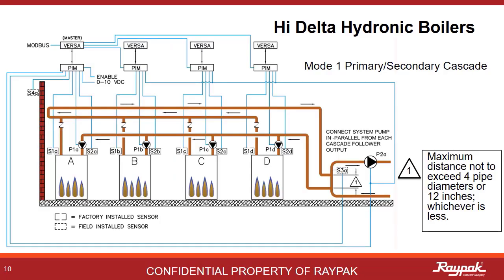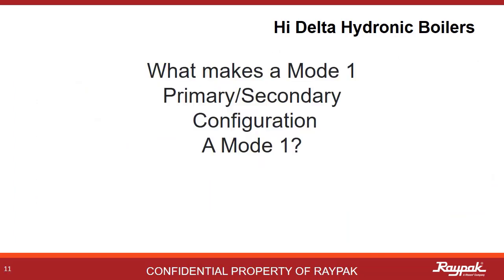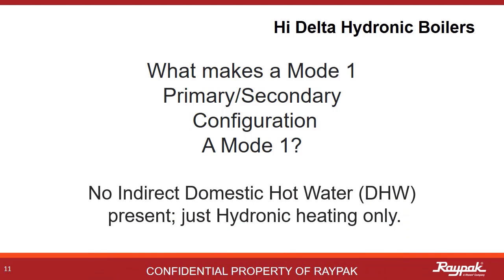This is the Mode 1 cascade system. Boiler A on the left is the master boiler, and boilers B, C, and D are the followers. All of the same decoupler concepts apply, only now they apply to the whole cascade. An important part of plumbing boilers in cascade is to use reverse return logic — the first boiler out to the loop is the last boiler to receive water back from the loop. What makes a Mode 1 primary-secondary a Mode 1 is not what's there, but what's not there: there's no indirect domestic hot water system present. It's just a straight-up hydronic heater.